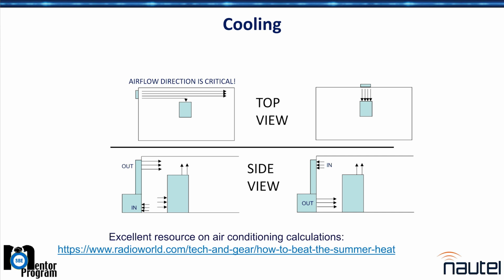In a case like this, I had one where I walked up and just threw an old hollow core door that was laying there against the side of the transmitter, created a baffle, and forced all the air through the box. Watched the operating temperature of the controller drop by almost 15 degrees Celsius in about half an hour.